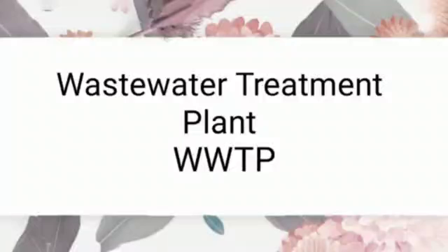For that, the first step is wastewater is passed through bar screens and large objects like rags, sticks, cans, plastics, packets, napkins are removed. Second step, water then goes to a grit and sand removal tank. The speed of the incoming water is decreased here. Why? To allow sand, grit and pebbles to settle down.